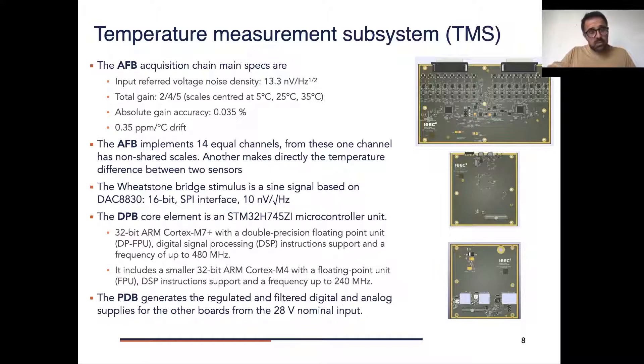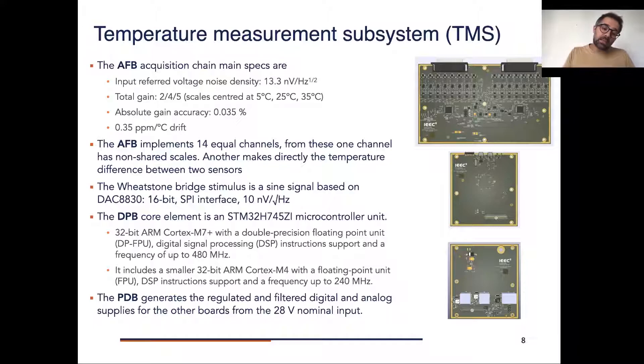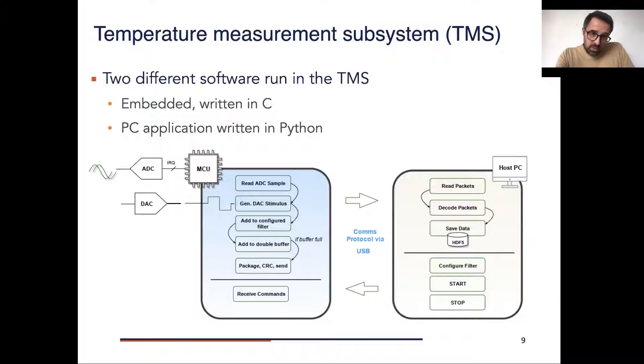The idea behind this measurement is again a Wheatstone bridge, but this time we are using a sine signal instead of a square signal as was used in Pathfinder. The digital processing has a microcontroller unit which allows for double-precision floating point, and also has support for digital signal processing and other features.